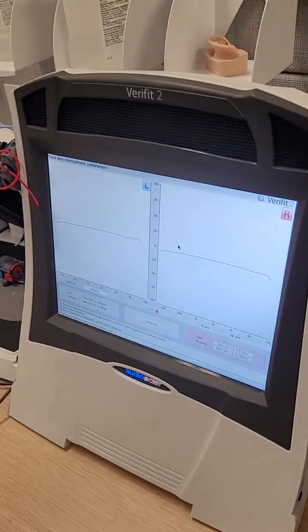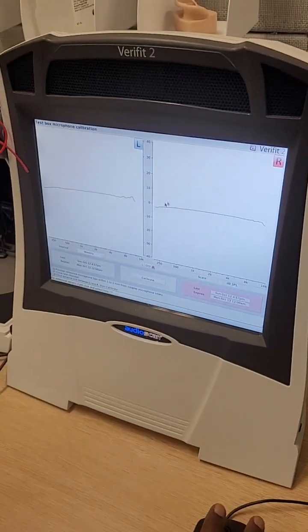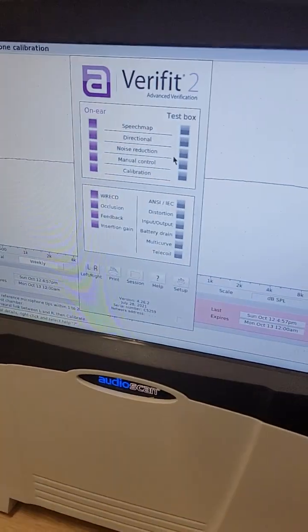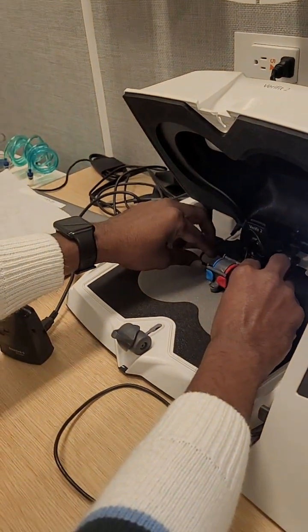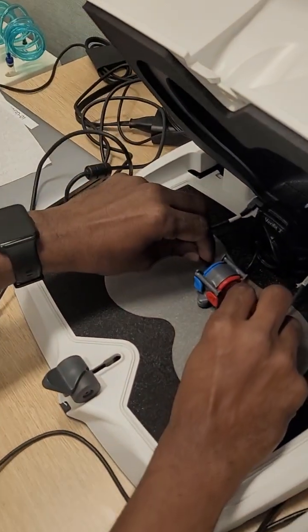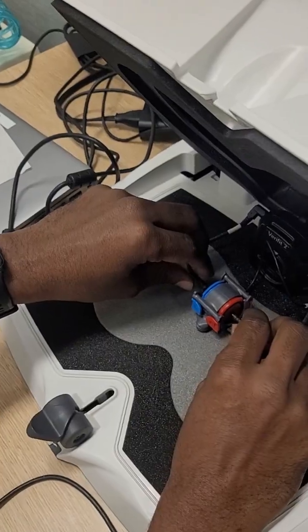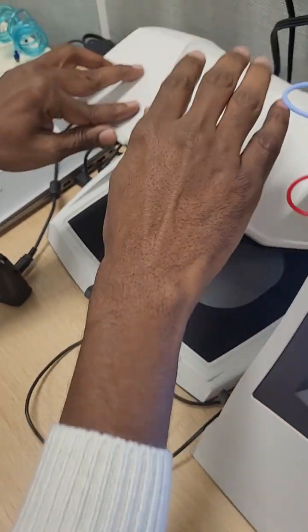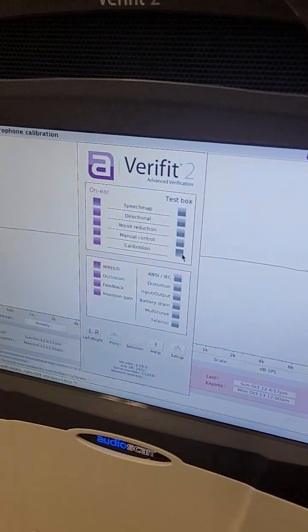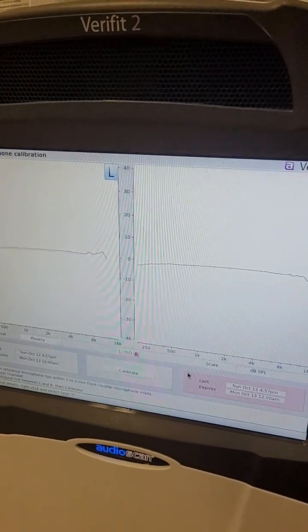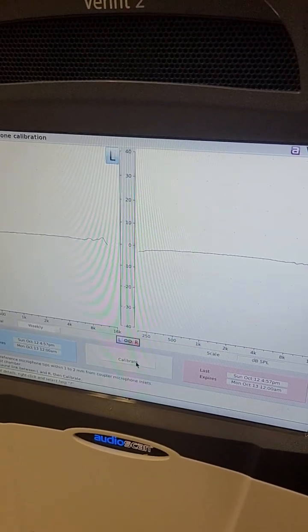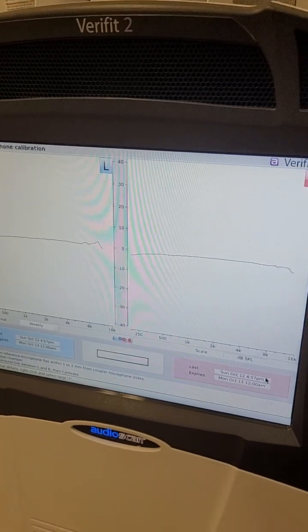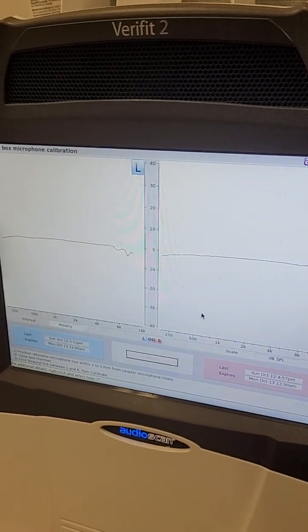As part of my verification, I'll be starting with the calibration and moving on to the next step. So as you can see here, we have to first do the test box calibration. This is my Verifit test box. I'll be bringing two reference mics on either side, close but not touching them though. Then I'll be closing the box itself for the soundproof sealing. Then go to the Verifit screen, do the calibration. I'll be choosing both sides and calibrate. So you get a flat line, good to go.